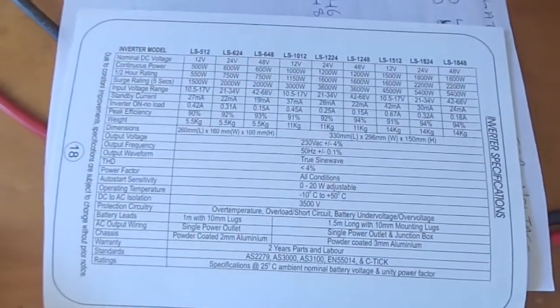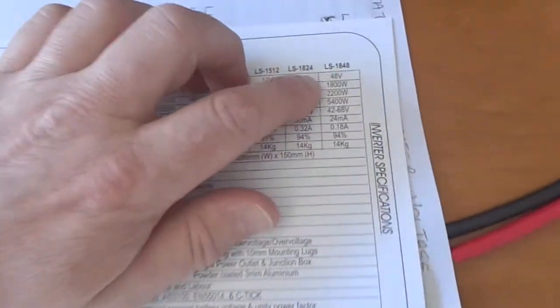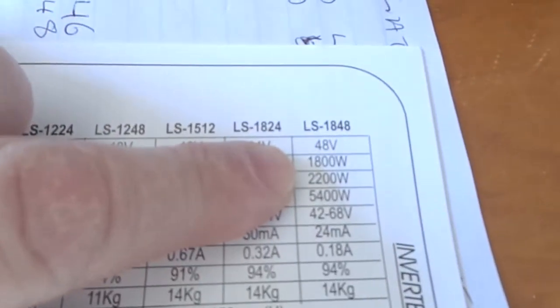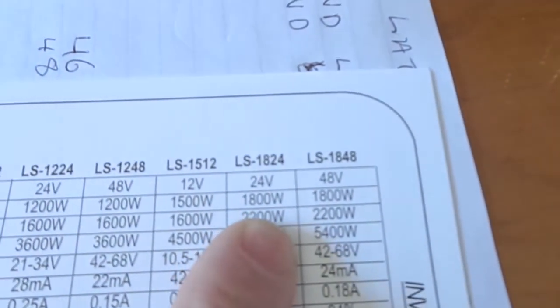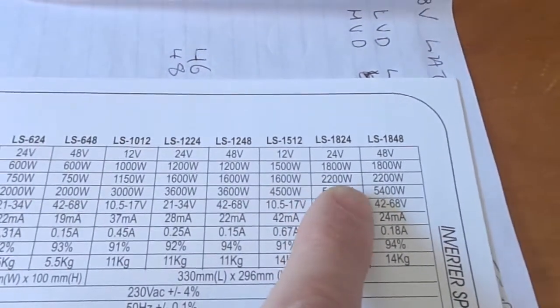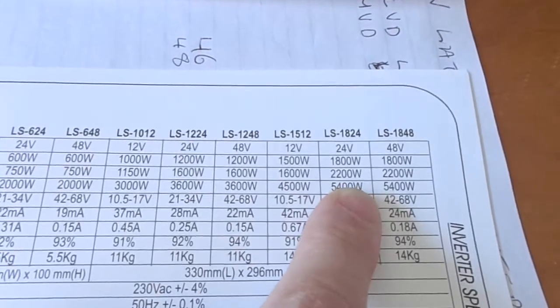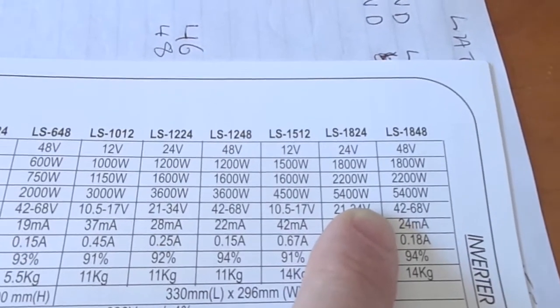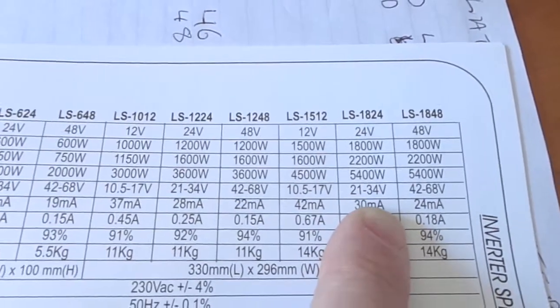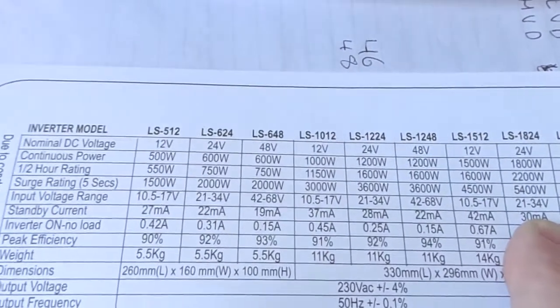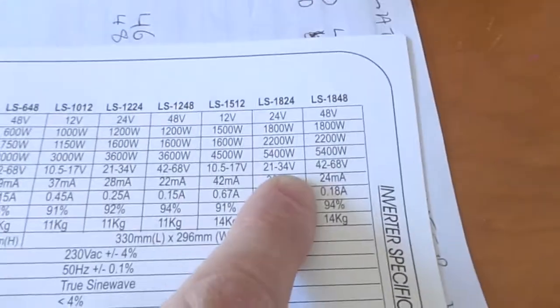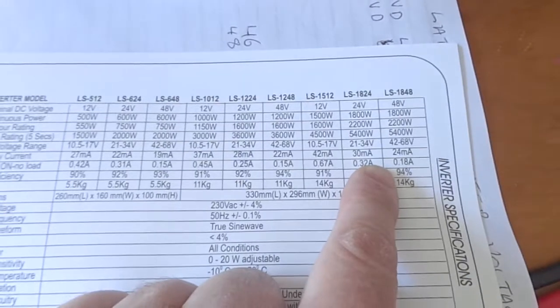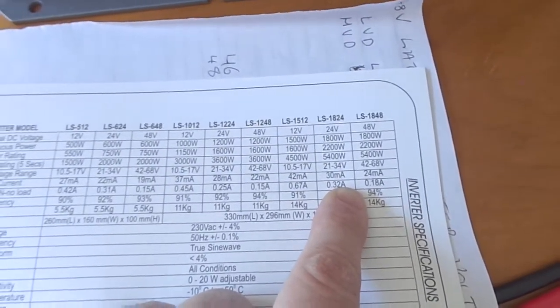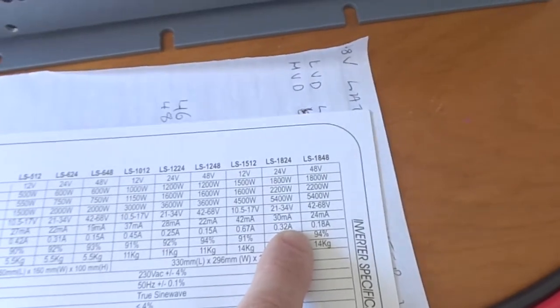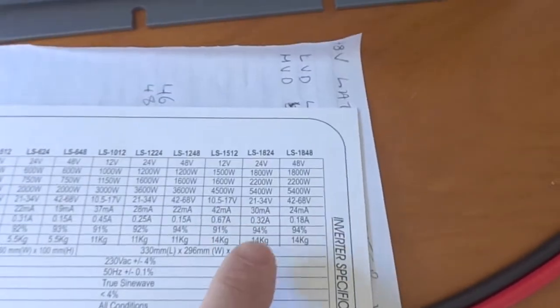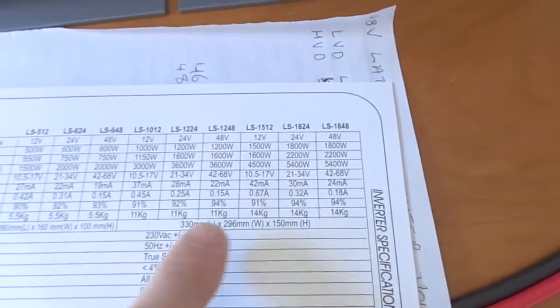Here's the specs on this inverter. You can have a look at this later if you like, just pause it. So we've got 48 volt, 1800 watt, 2200 half hour rating, 5400 watt 5 second surge, voltage range 42 to 68 volts. Standby current 24 milliamps. Inverter on, no load, 0.18 amps, peak efficiency 94%, the weight is 14 kilograms, there's the dimensions.